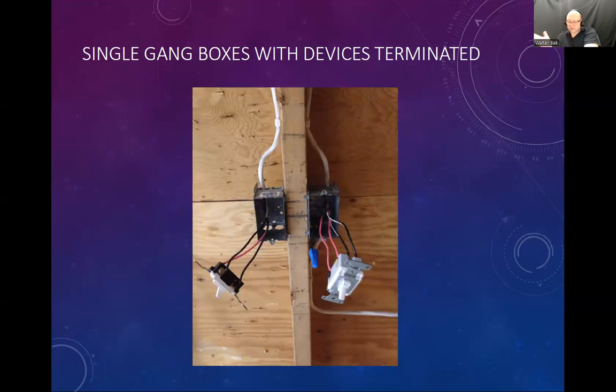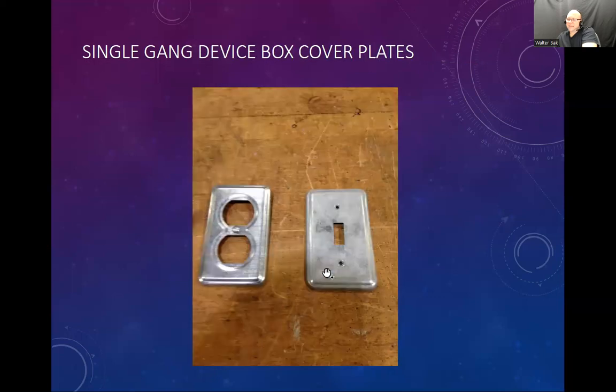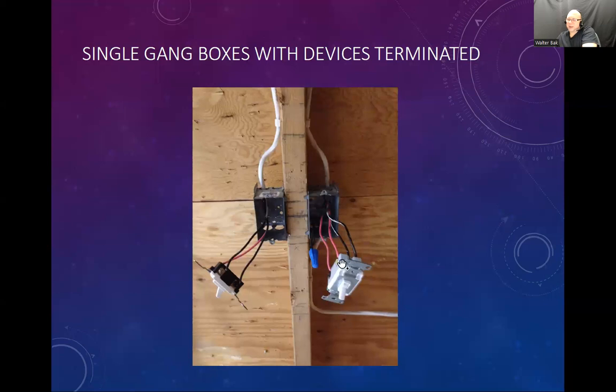So again, when you study code, you're going to find out where those GFCI rated circuits should be applied, and mostly it's going to be wherever there's access to water and there's certain distance of that. So all the bathroom outlets or the bathroom receptacles, all the kitchen by the countertop where there's access to water, they are supposed to be GFCI. But those, well, this is not that one, but it looks a little bit bigger than just a regular duplex receptacle, then it is going to occupy a little bit more space, right?